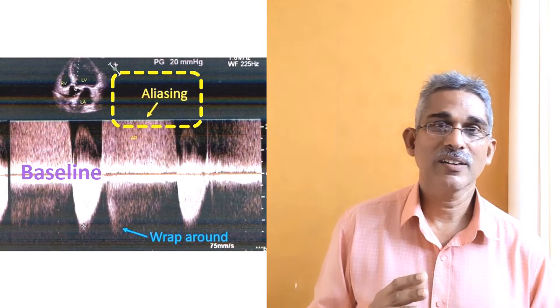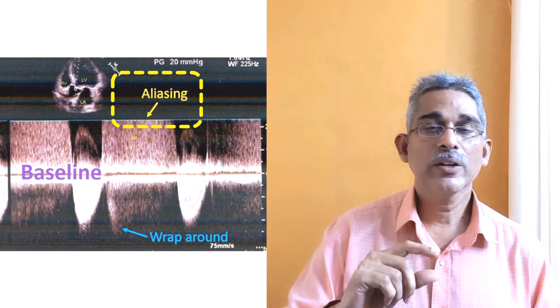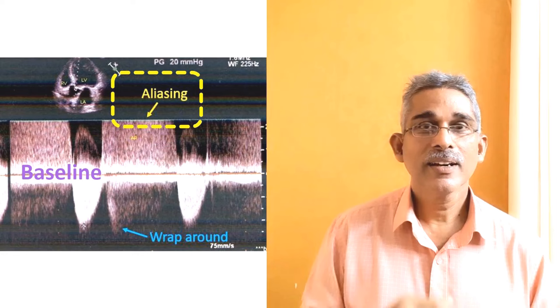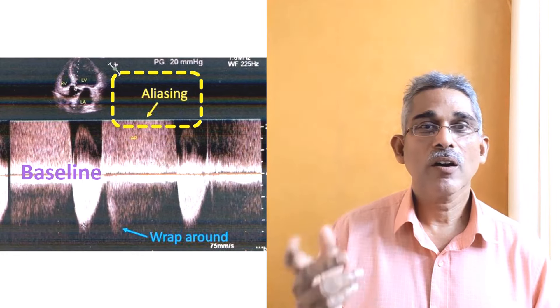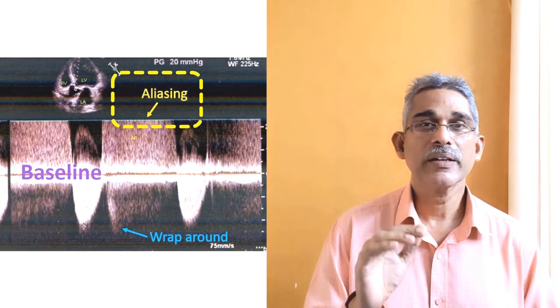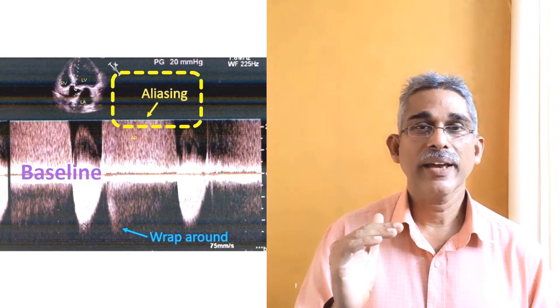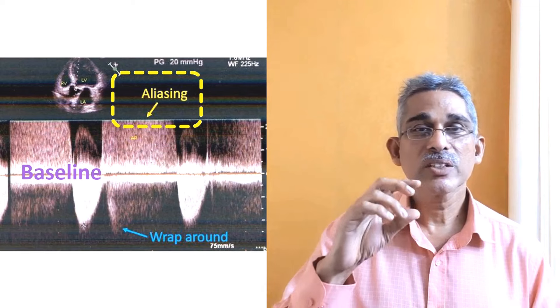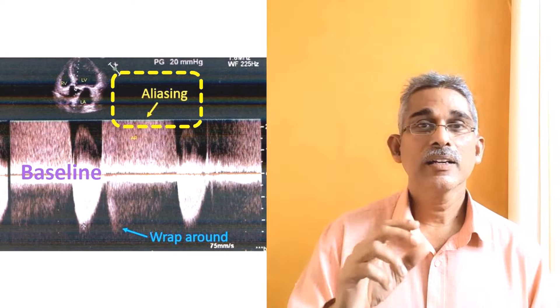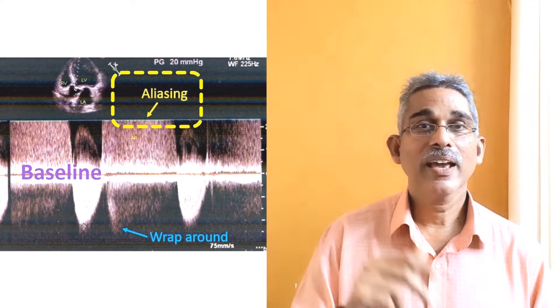In echocardiographs you can change the settings by shifting the baseline upwards or downwards or by increasing or decreasing the velocity ranges to manage aliasing. Once you get aliasing, either change the baseline or change the velocity limit so that you get a non-aliased signal on the screen before identifying the direction and maximum velocity of the signal.